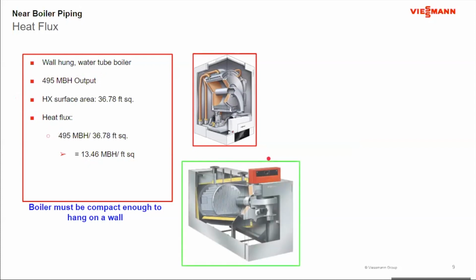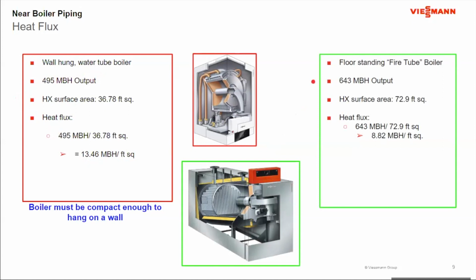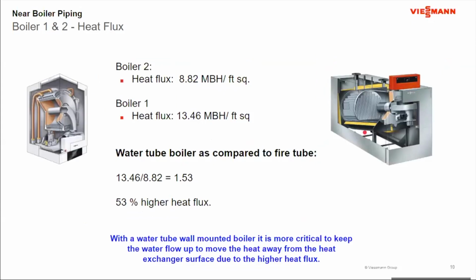Now, if I go to the floor standing boiler, I have 643,000 BTU output. The heat exchanger is about 73 square feet. If I do the math, I get 8,820 BTUs per square foot. Much lower heat flux compared to the wall-hung boiler. If I ratio these two, I take my 13.46 over here versus my 8.82, I get 1.53, which is telling me that the heat flux within this boiler is 53% higher than the heat flux in this boiler here. So on the surface of the heat exchanger per square foot, I have 53% more energy that I have to move off the face of that heat exchanger.